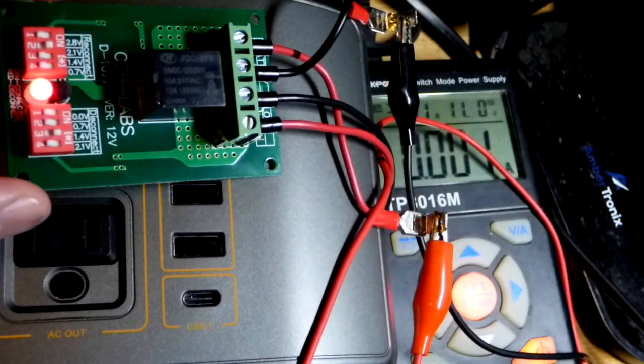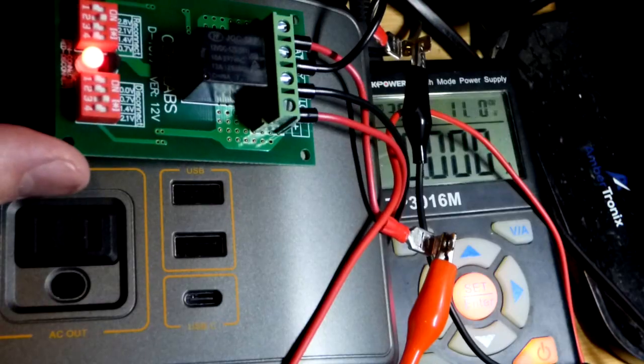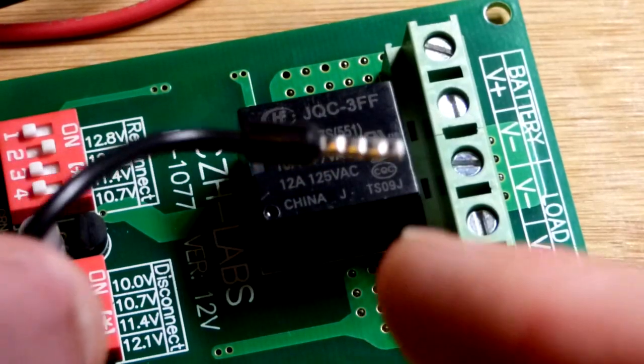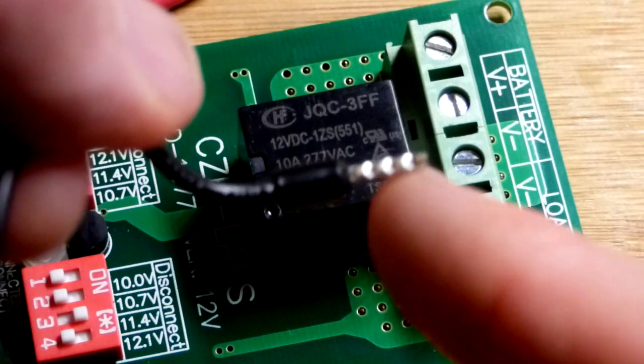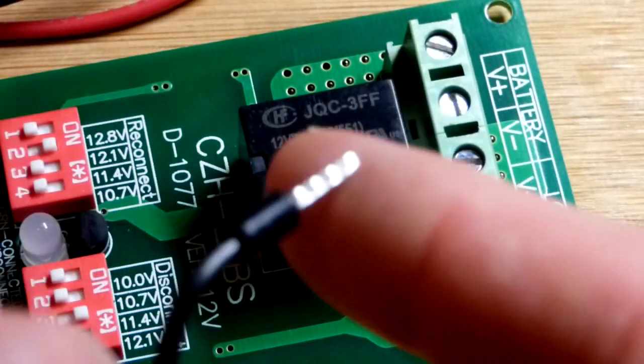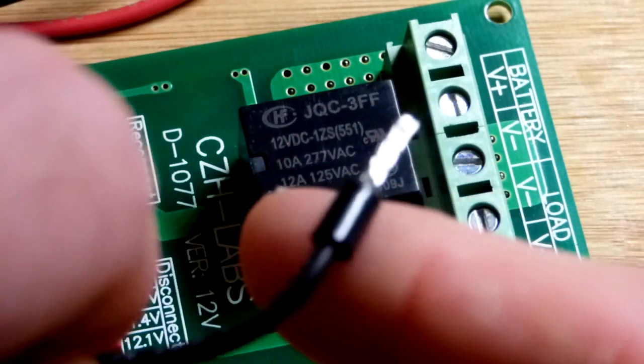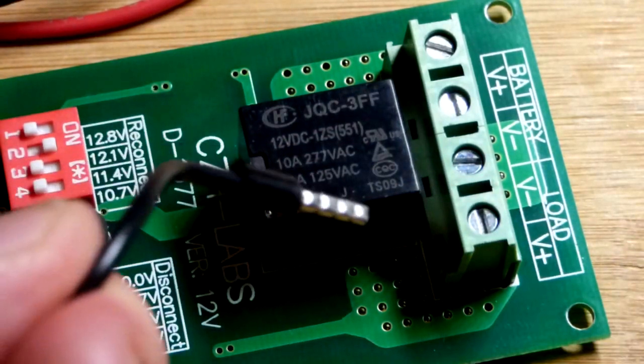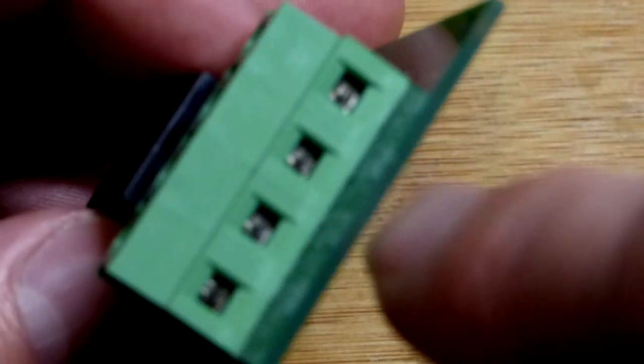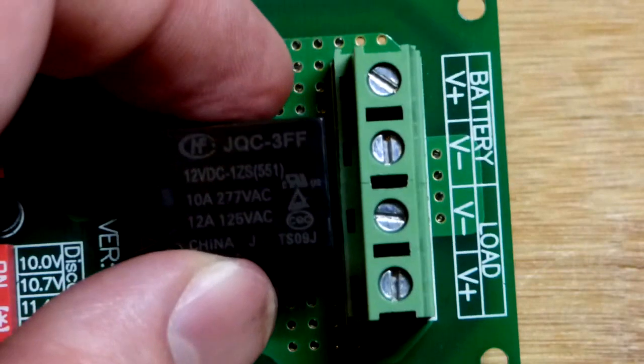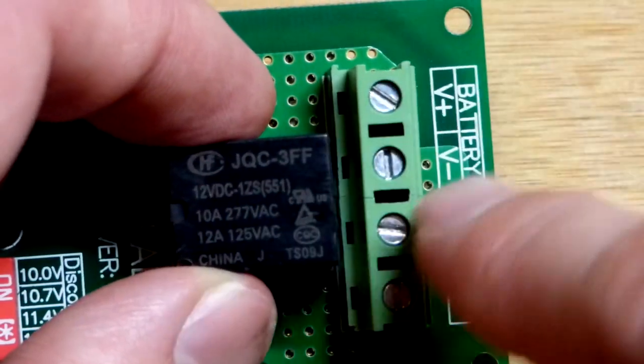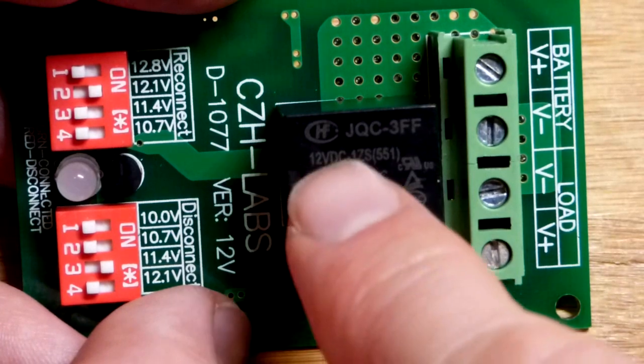A couple other things really quickly. This is a ferrule connector, so that was a round tube. We slid it onto the wire and then the crimper crimped it into this shape. My crimper makes a square shape like that with the little ridges that hold on to the wire. Then you slide the connectors into the slots there. There is extra room here, you could probably go up to the next higher size, and then you just screw it down.